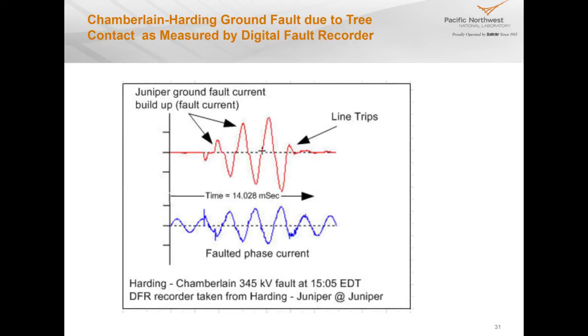Now the way these maps work is the thing in yellow is the other line that I showed. So if it's in yellow, it's from previous slides, and if it's in red, that's the one on this slide. So right next door, another 345 kV line tripped. It was also a tree trip. Tree contact got too close. Now this is a picture taken on that day of that line. They were out working on it.